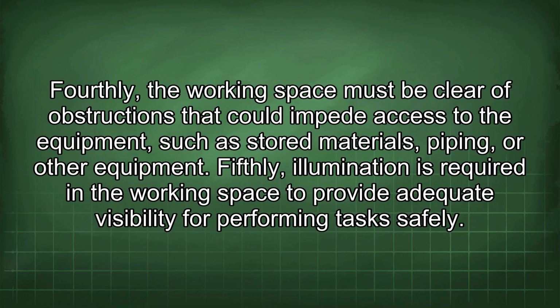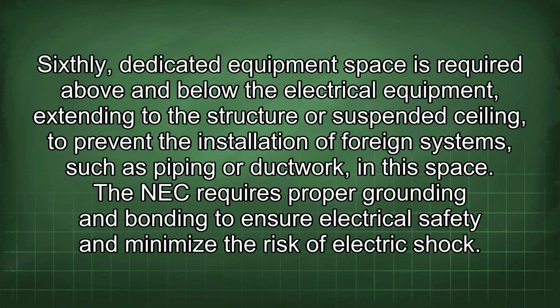Fourthly, the working space must be clear of obstructions that could impede access to the equipment, such as stored materials, piping, or other equipment. Fifthly, illumination is required in the working space to provide adequate visibility for performing tasks safely. Sixthly, dedicated equipment space is required above and below the electrical equipment, extending to the structure or suspended ceiling, to prevent the installation of foreign systems, such as piping or ductwork, in this space.